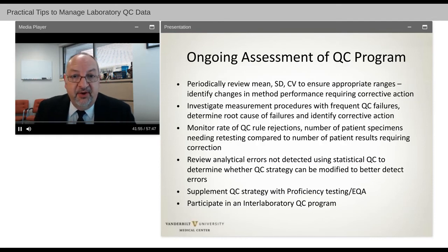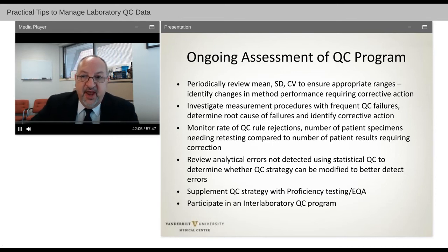You want to periodically review your means, SDs, CVs to ensure appropriate ranges, identify changes in method performance that may require corrective actions. Certainly investigate measurement procedures that have frequent QC failures. Redetermine whether you've had a shift in the performance or a deterioration in your reagent or even the quality control material itself. So look to peers. Monitor the rate of QC rule rejections, your number of patient samples needing retesting. Review your analytical errors not detected using statistical QC to help you develop a better QC strategy and better appropriate multi-quality control rules.